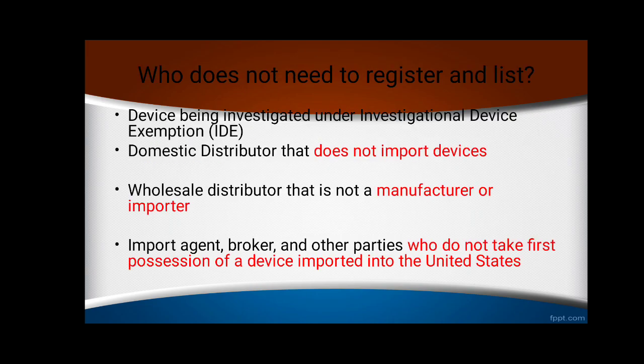But the FDA has exceptions: if your facility is one of them, you are not required to register and list with the FDA. For example, if your device is a device under an investigational device exemption, IDE, you will be exempt from FDA registration and listing.